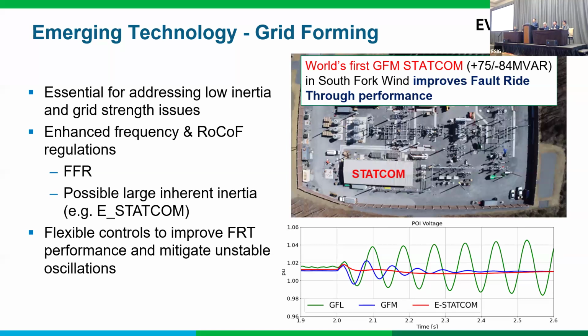eSTATCOM is also a grid forming STATCOM with supercapacitors. According to the vendor, it also has a larger inertia, which is 10 times larger than a same-size condenser. It's amazing. On the diagram below, I show you a comparison of grid forming STATCOM, grid following STATCOM, and eSTATCOM. The blue line is the grid forming STATCOM. You can see that it mitigates uncontrolled oscillations and meets the performance requirement of 3% damping ratio. And the eSTATCOM is even better, it completely removes the oscillation mode.